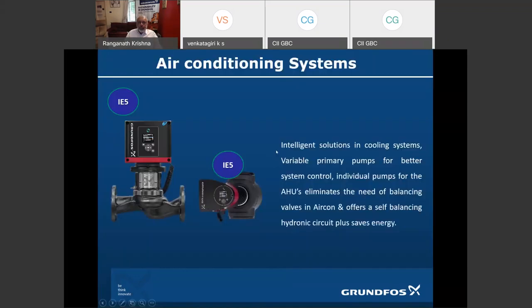The next one is air conditioning. I spoke about air conditioning already. Intelligent solutions in cooling systems. There was variable primary before, then they came with the variable secondary and primary came together. Then we had two-way valves replacing three-way valves in the AHUs.